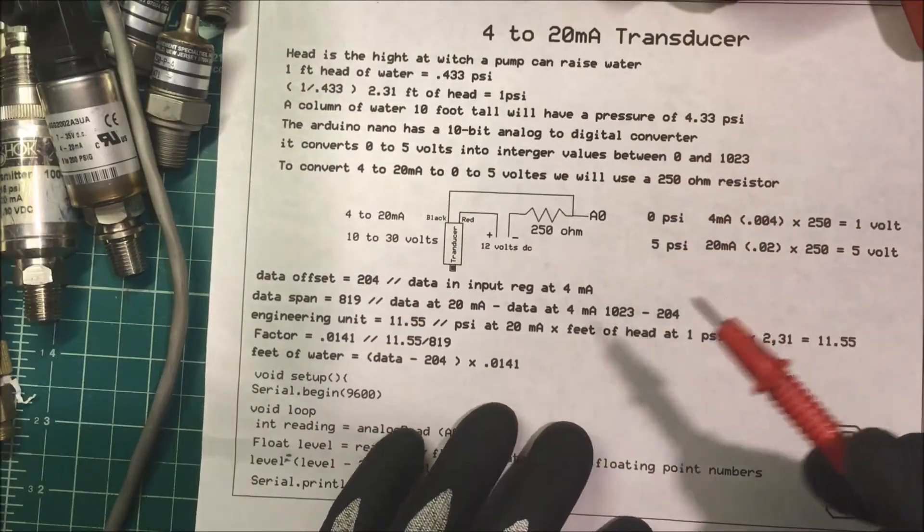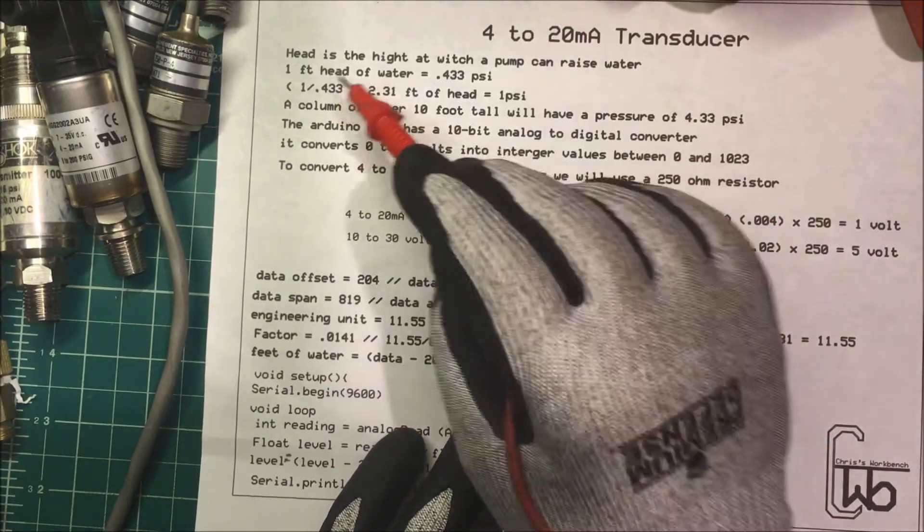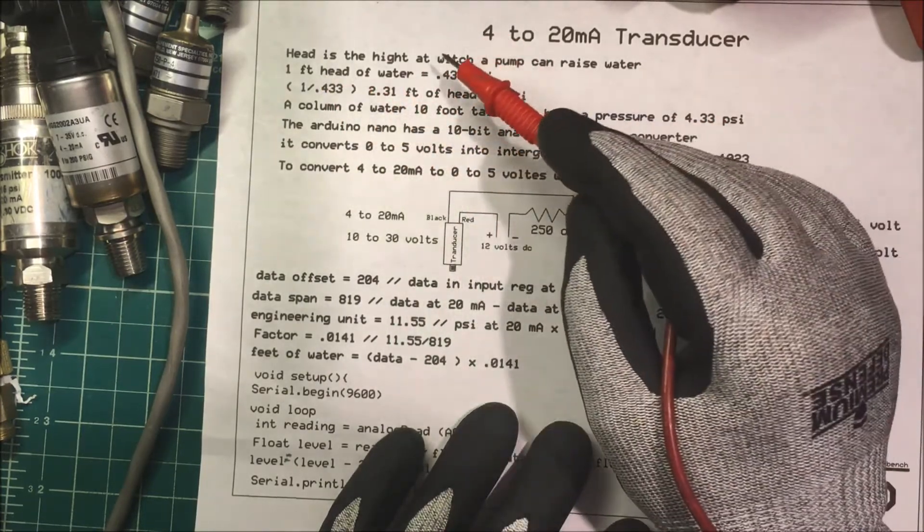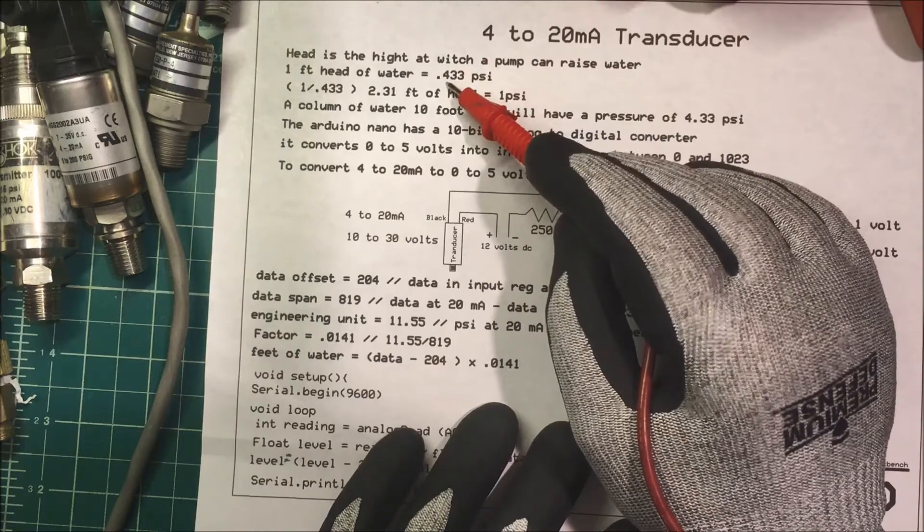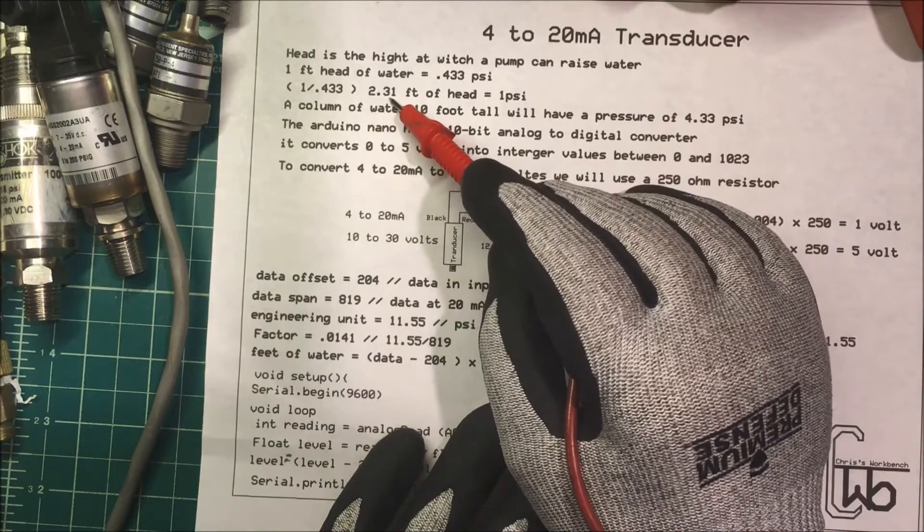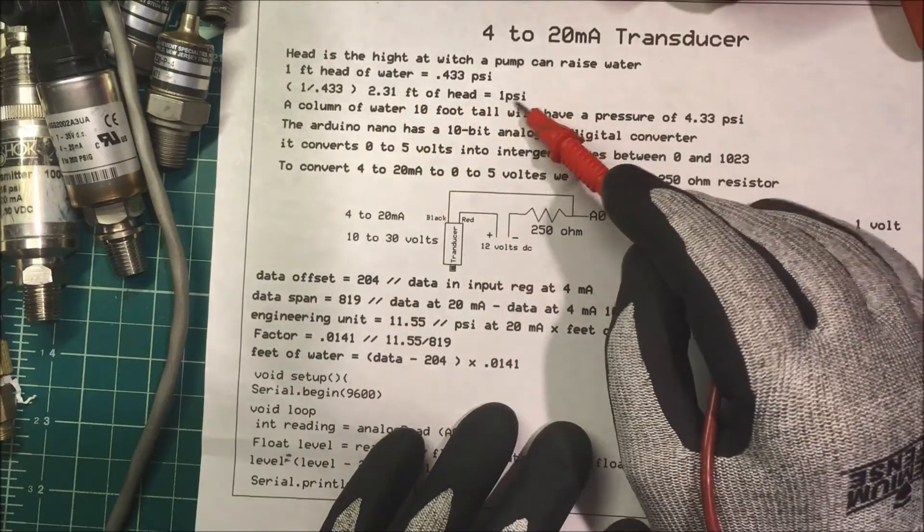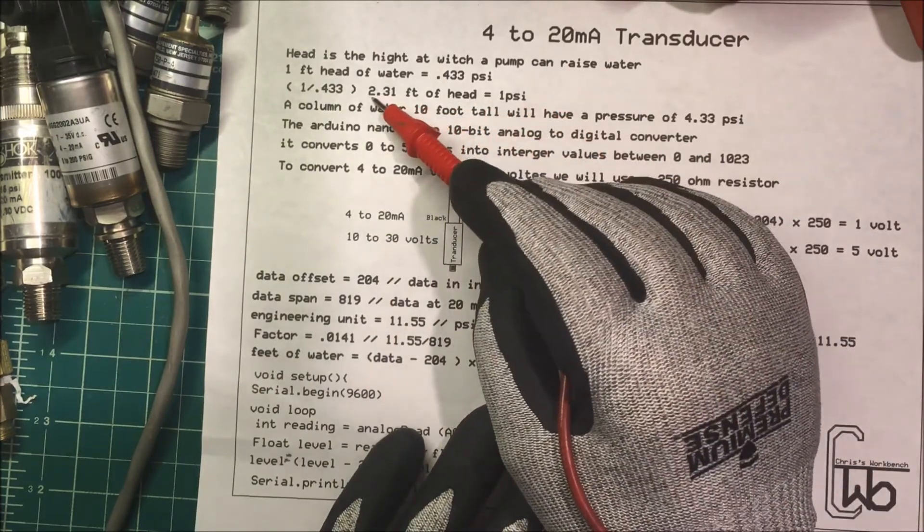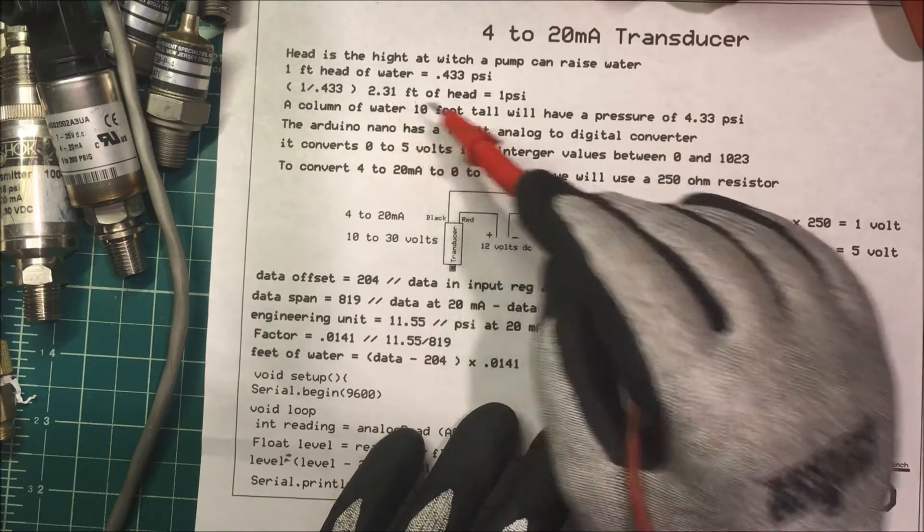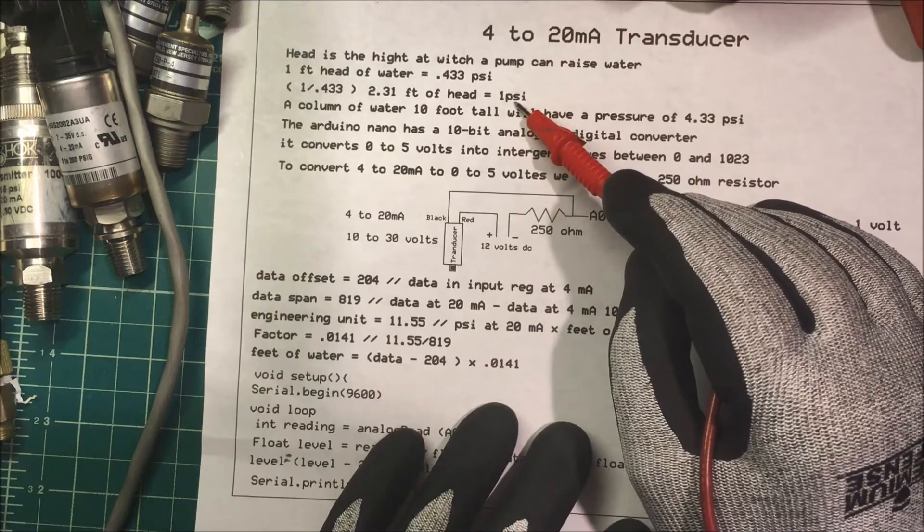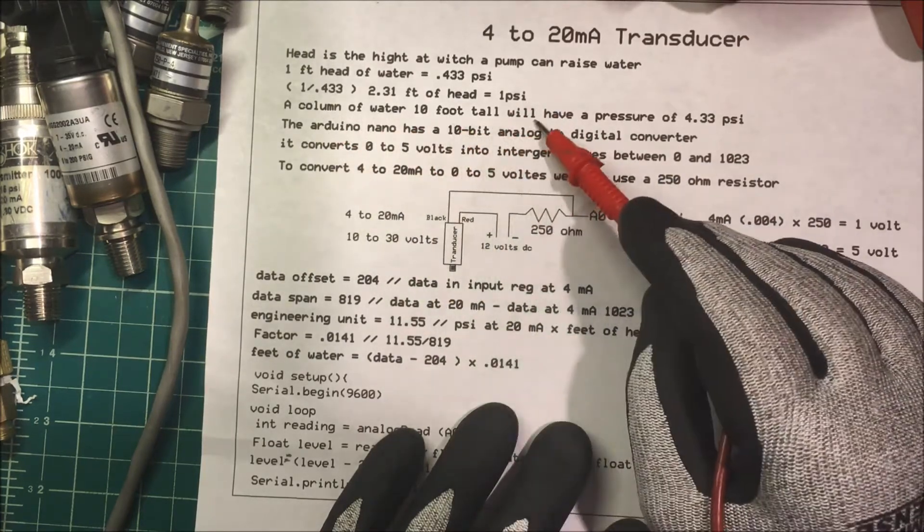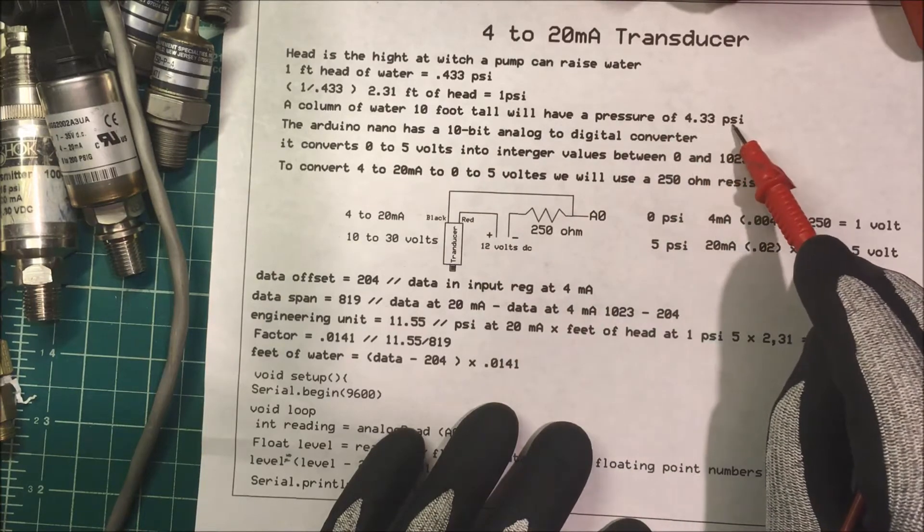So we need to know some terms. Head is the height at which a pump can raise water. So one foot of head is equal to 0.433 psi. If you take the reciprocal, 2.31 feet of head is 1 psi. So that means a column of water that's 2.31 feet tall exerts a pressure of 1 pound per square inch. So a column of water that's 10 feet tall will have a pressure of 4.33 psi.